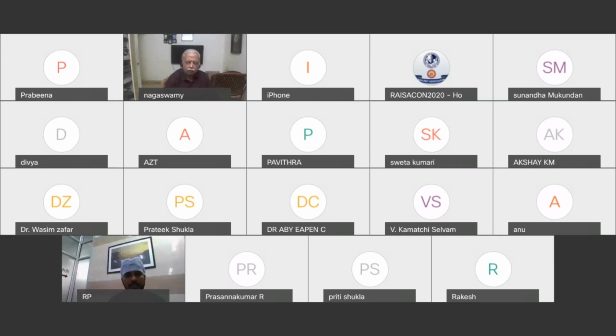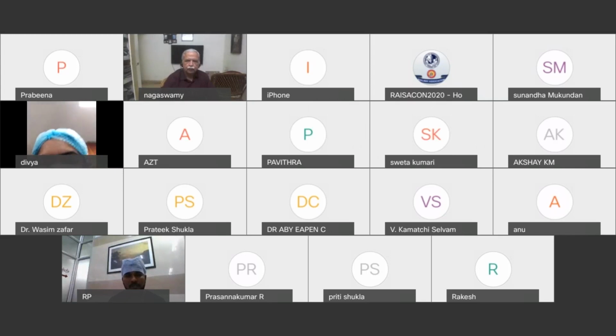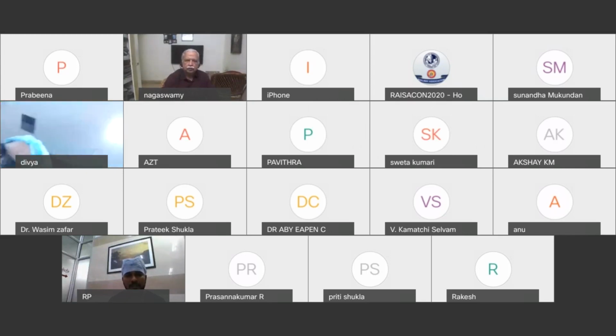And the common gas outlets. Nowadays, some machines have extra common gas outlets also. All these things you have to mention. Instead, you can first classify the various levels at which the safety features are, and then divide them into high pressure zone, intermediate pressure zone, and low pressure areas. Then it will be easy to remember and also to narrate your answer.